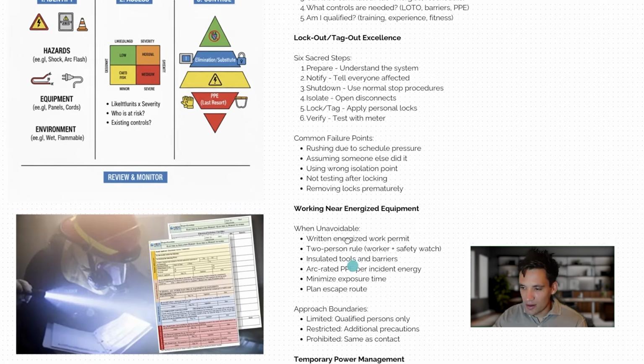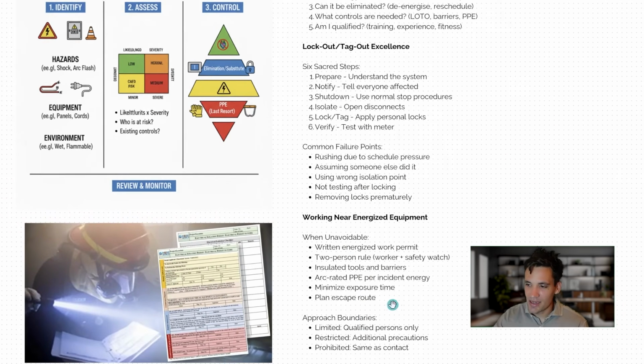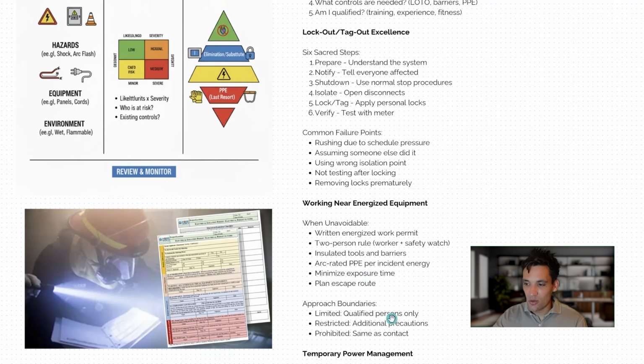When it's absolutely unavoidable, and in certain situations it is, there will be situations where people need to work near or on energized equipment, in which case they'll need insulated tools and barriers. They'll always need to work in groups of two, so you have a worker and a safety watch. They'll need to understand electrical rescue procedures. They'll need arc flash rated PPE dependent on the expected level of fault current. So you can see a situation here where someone's dressed in arc flash rated PPE, and they'll also need to minimize their exposure time.